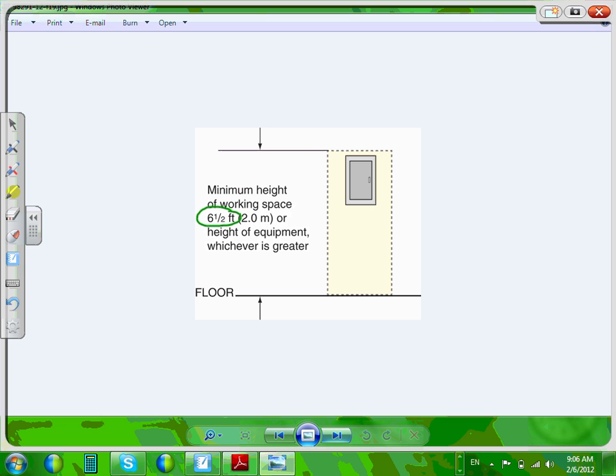So I have the working space. I know the width is the equipment width or 30 inches. But how high can I go? Look at this, 6.5 feet or the height of the equipment. So if I have a switchgear that goes all the way to 92 inches, right? That's going to go all the way up to 92 inches. How much is 6.5 feet? How many inches? 78. So if you have a 92-inch switchgear, the working space goes to 92 inches.